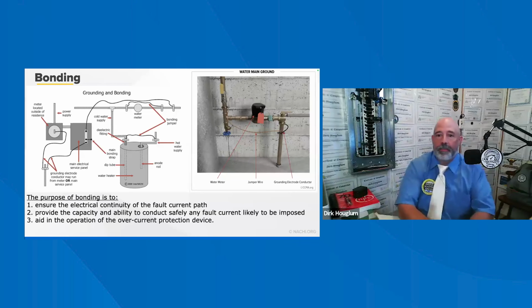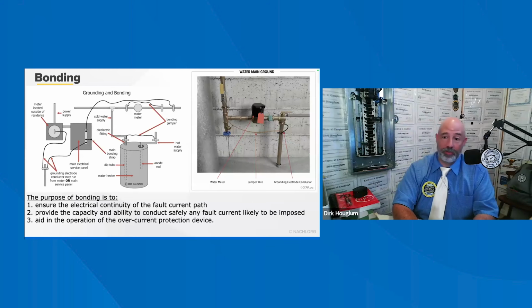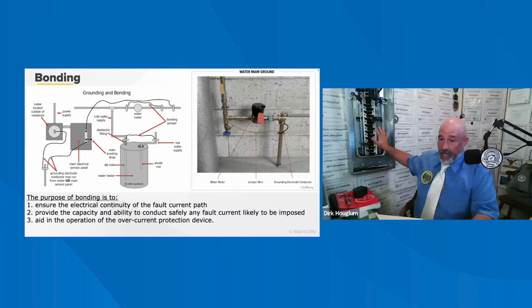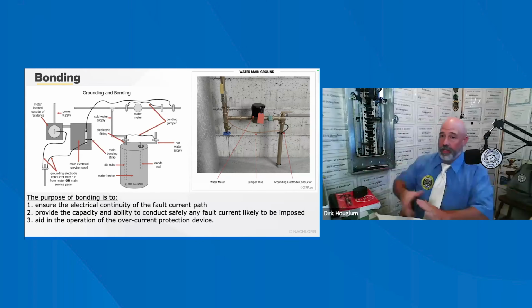Okay. At the main service panel board, the initial main disconnect, neutral conductors (white wires), equipment grounding conductors (the bare copper or the green insulated wires), the metal service panel board cabinet, and the grounding electrode system must all be bonded together. The code requires that the grounds and the neutrals be kept separate except at the main disconnect. So if this is the main breaker, this will be connected. After this, they have to be separated.